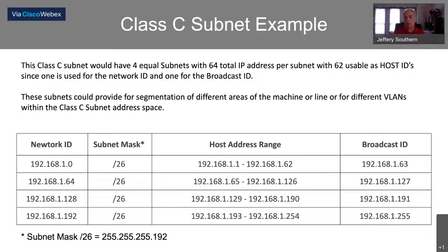I might do all processor-to-processor communication on the .64 network, all my drives and IO on .128, and reserve .192 for other uses, maybe communication between a SCADA system and this device. It's a way of segmenting data between subnets so there's no possibility of traffic accidentally crossing over into another subnet.